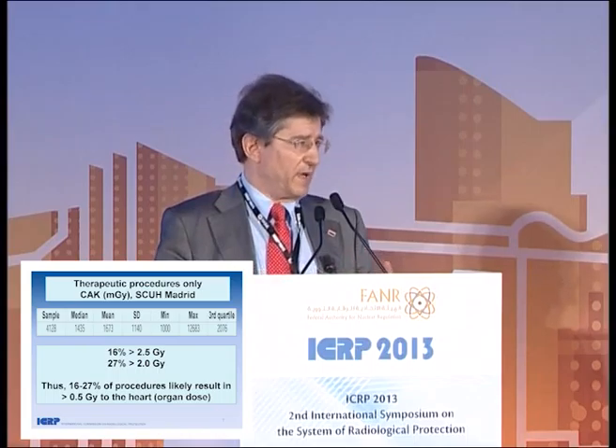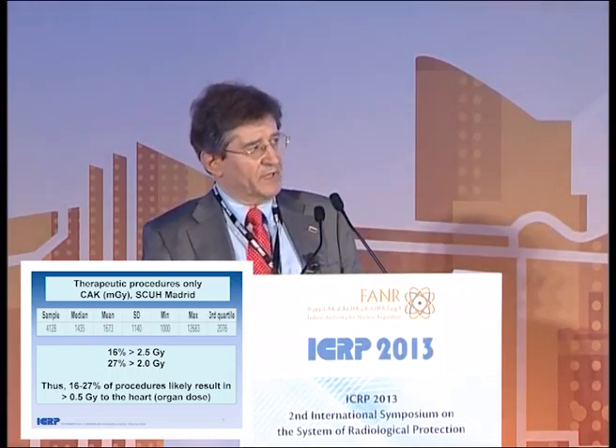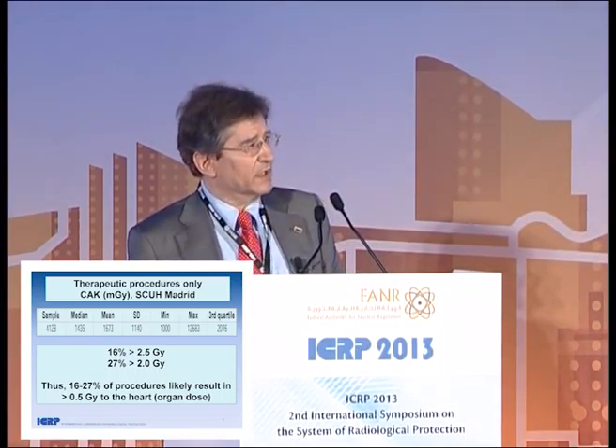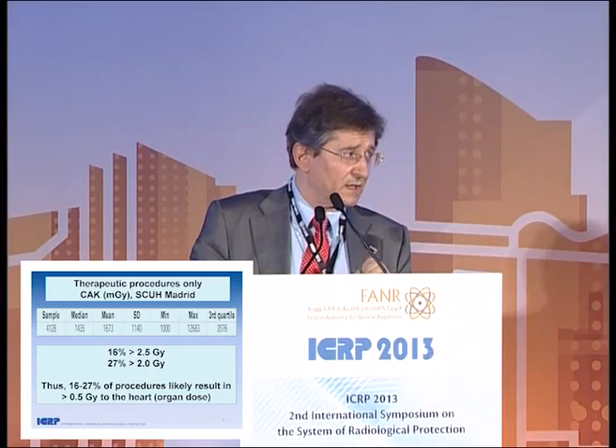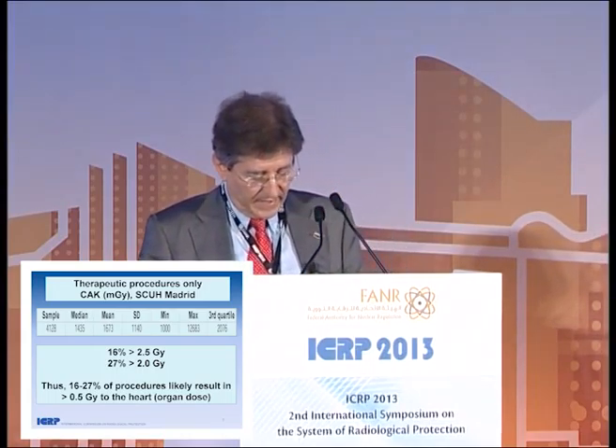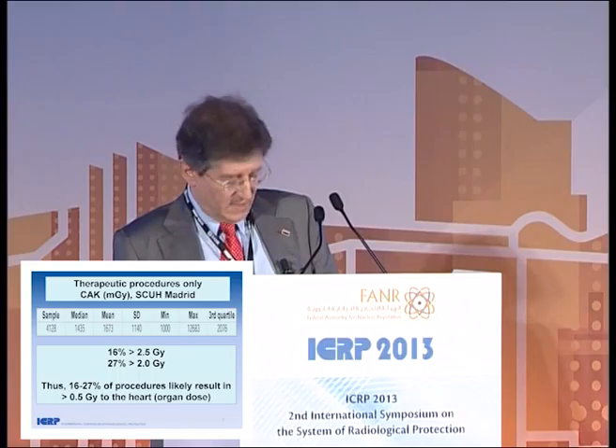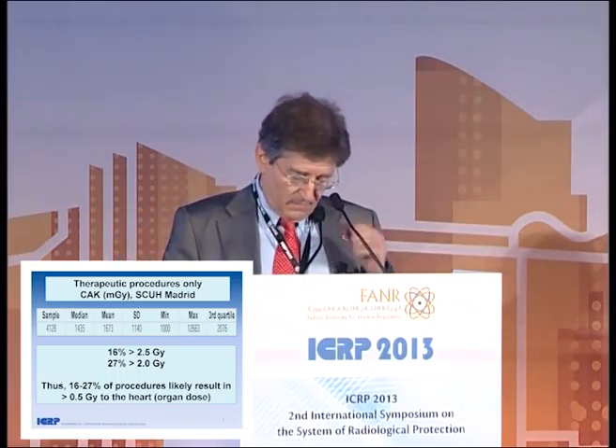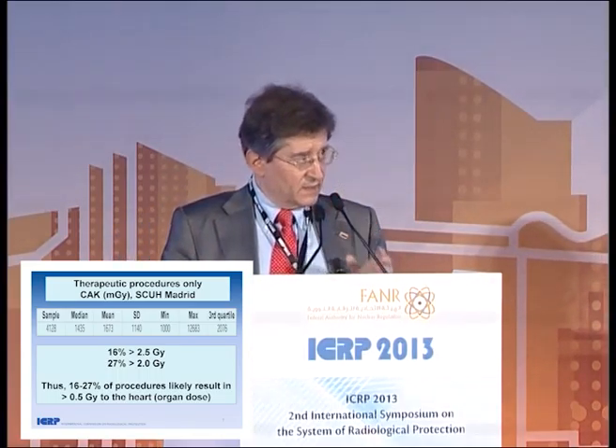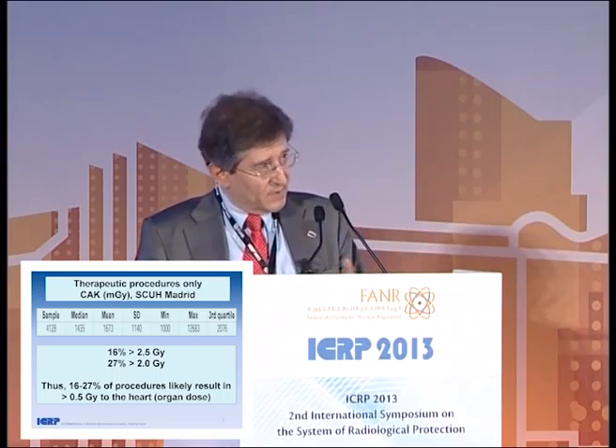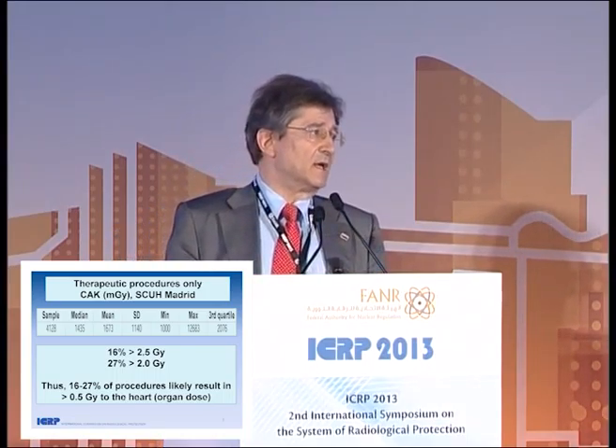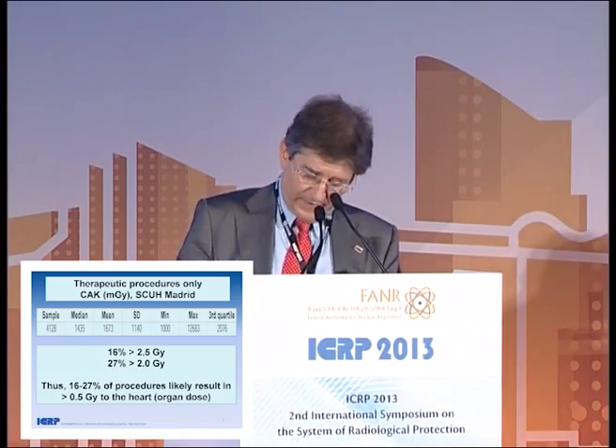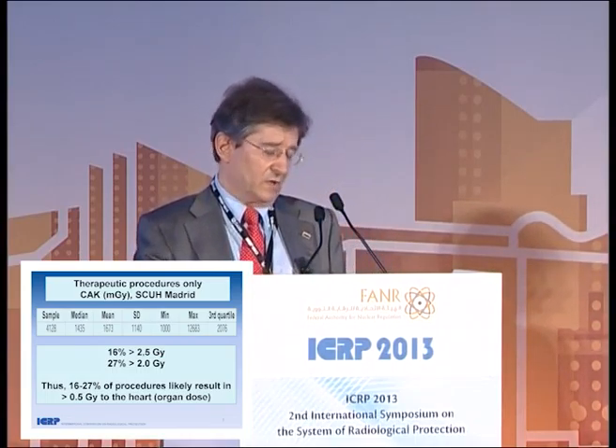If we move to therapeutic procedures — all the complex ones including PTCA, simple PTCA, and total coronary occlusions — 16% could have a cumulative air kerma higher than 2.5 grays, and 27% have a cumulative air kerma more than 2 grays. This range means between 16% and 27% of procedures likely result in a heart organ dose higher than 0.5 grays.